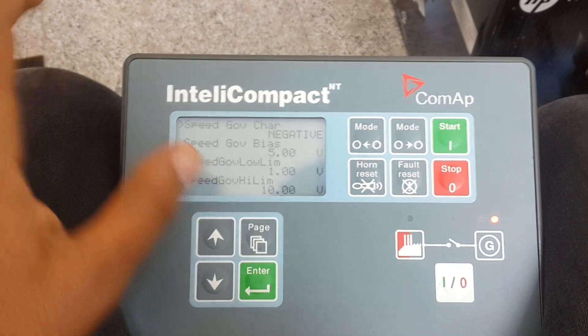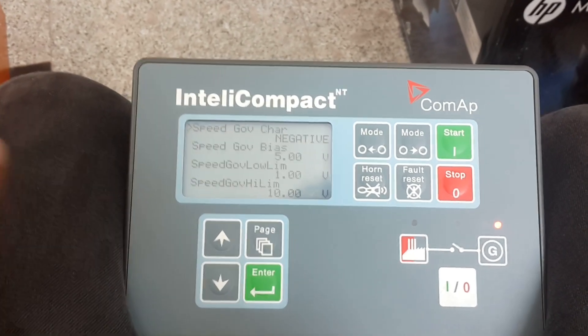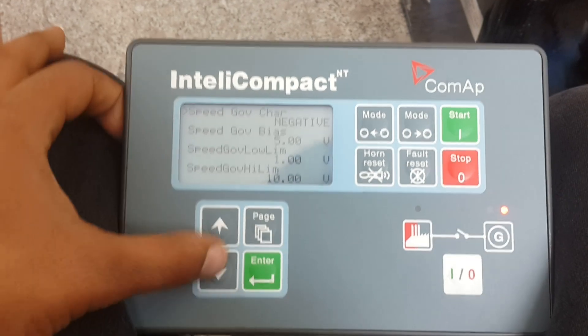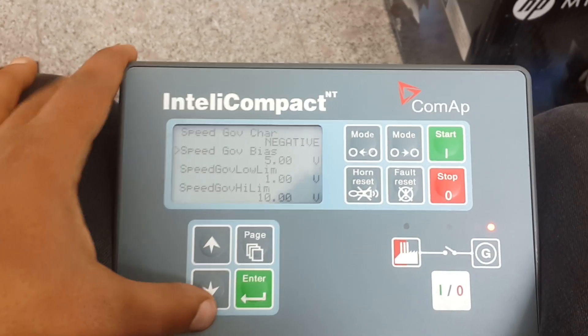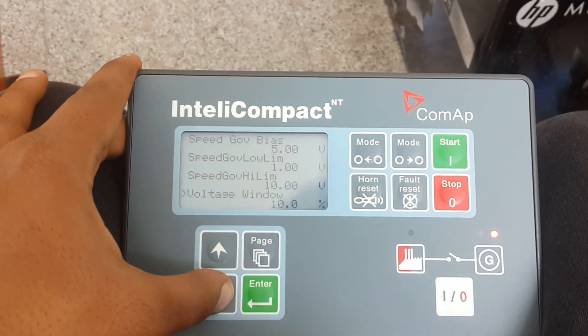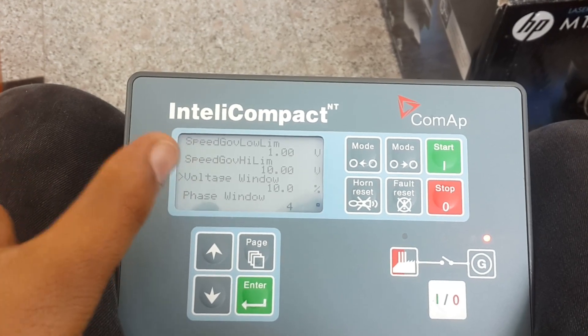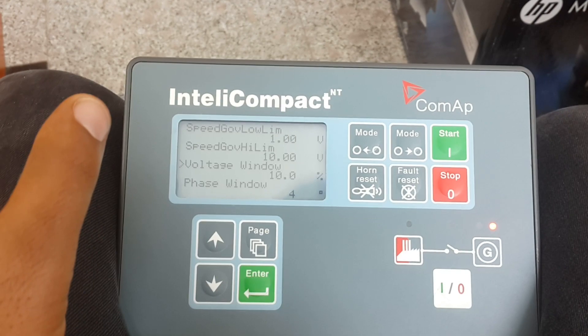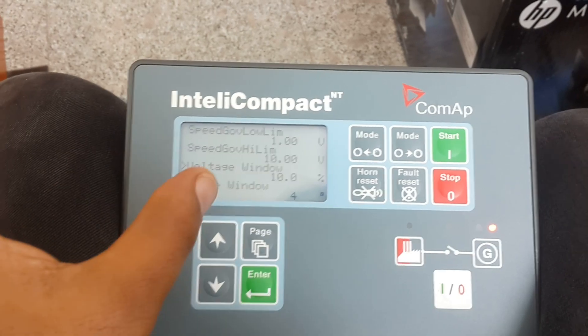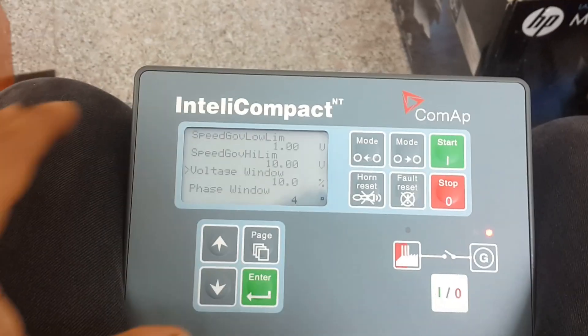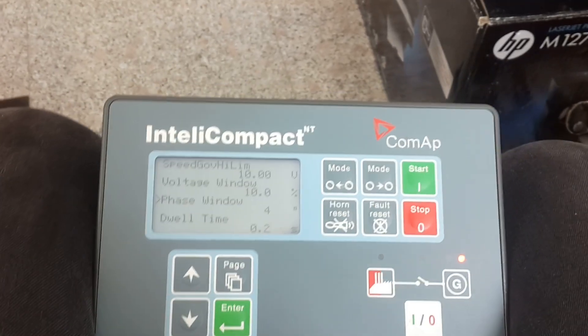Sync speed governing character is a negative type — there are two types of governing characters, positive and negative. Just take a look at that before you do your syncing. Speed governing bias — this is a very essential part — speed governor low limit, speed governor high limit. Voltage window: this is the window that, before syncing, the controller checks if the two gen sets or more are within that level. It will automatically check if the voltage is within the limited window.